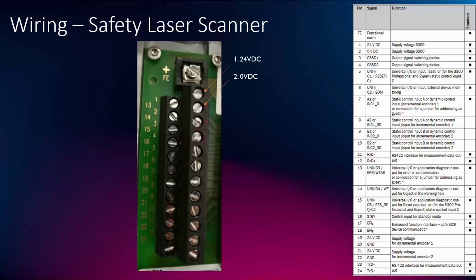The pins number 3 and 4 are the OSSD outputs of the safety device, labeled OSSD1 and OSSD2. Like we saw in a previous slide, these can be wired directly to the robot controller's designated safety input or to an external device. At pin number 5 we have the reset input, which can be used to reset the device in case of a safety violation and bring the device back to its normal operational state. The pin number 6 is the EDM input, which can be used to monitor the state of an external safety device, such as a safety relay or a safety logic.